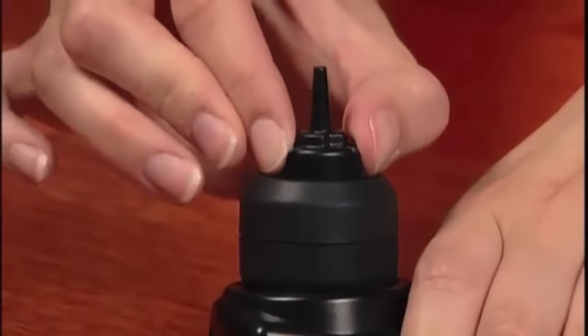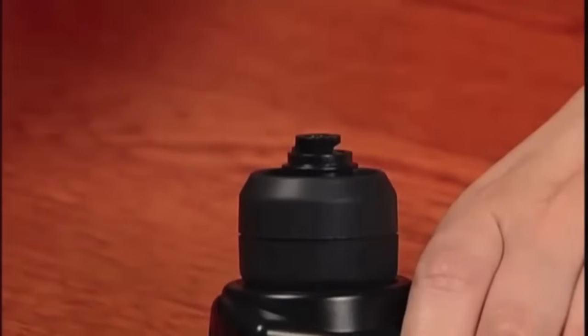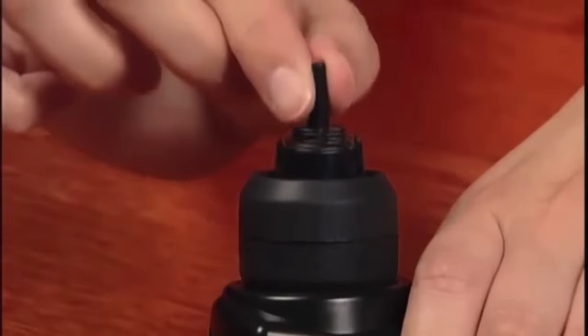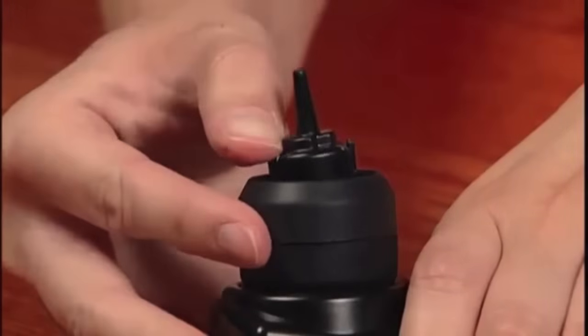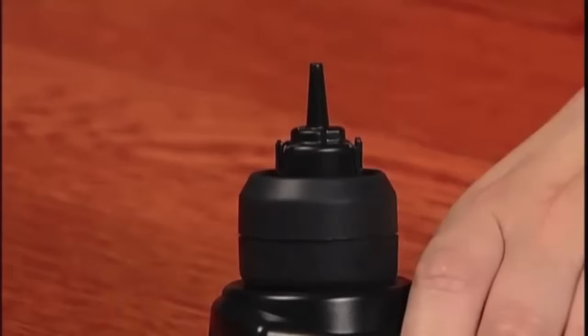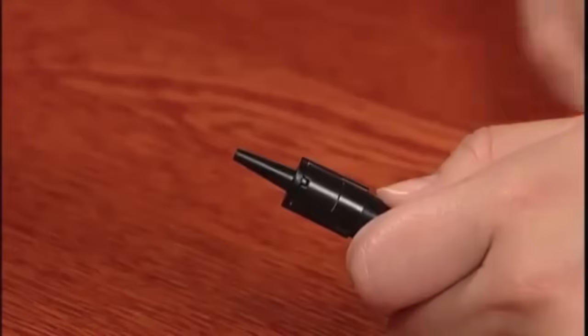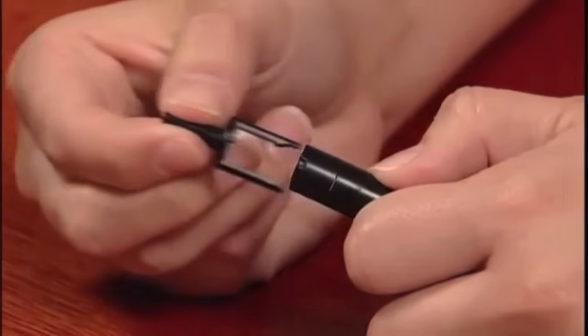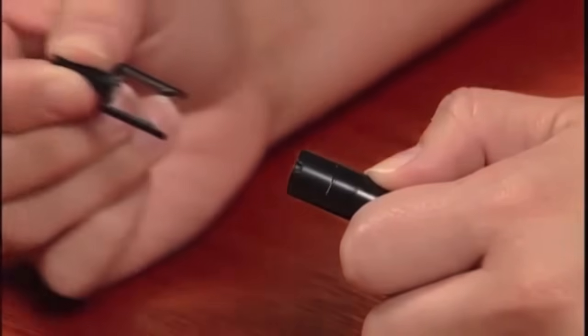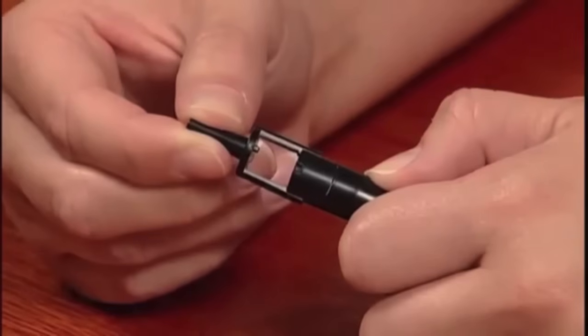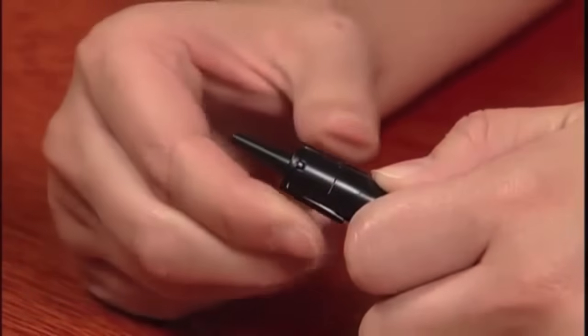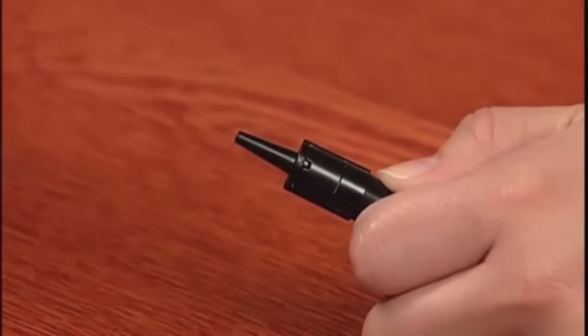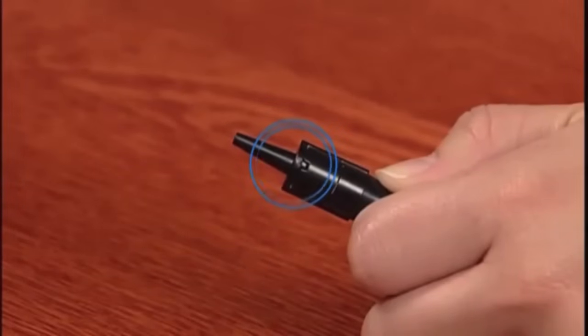To replace the tip on the handheld unit, squeeze the tabs and pull the old tip off. Discard the tip. Place a new tip on the probe and push down on one tab at a time until it clicks into place. Be sure to tug lightly on the probe tip to verify that the tip is securely attached. To replace the tip on either of the external probes, release the tabs on either side of the probe and slide the tip off. Discard the tip. Align the replacement tip using the notch on the end of the probe and slide into place. Once the tip is pushed all the way on the probe, press lightly on the tabs to snap them into place. If seated properly, the tip will be flush with the body of the probe. Since the Ero Scan Pro is designed to be easy to use, this is all it takes to keep your unit in tip-top shape for years to come.